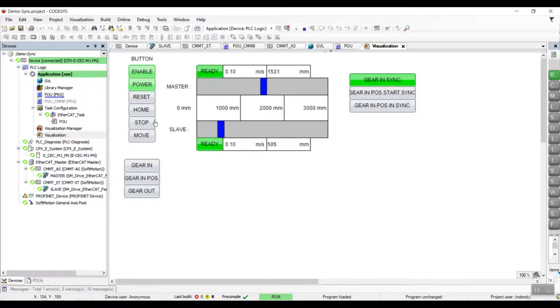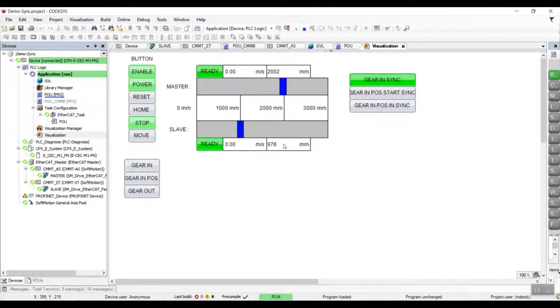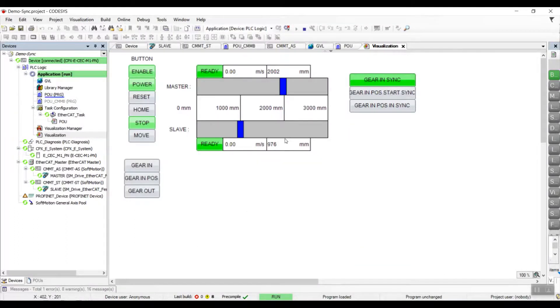We will now stop the master and observe the position difference between master and slave. We can see there is a difference between the master and slave positions. This is because the slave will only start accelerating to the target velocity when the master has reached the position of 1 meter. It takes some time for the slave to build up the velocity, hence the difference in position.